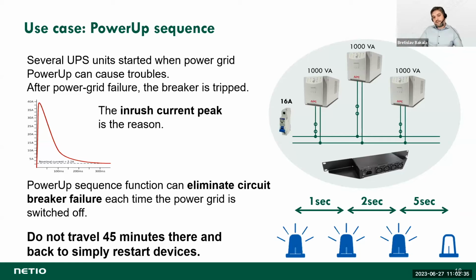This inrush current is the reason why. It's not an issue just for UPS, but for all standard switching power supplies used in every IT equipment today, even laptops and monitors. It depends whether you have bigger servers, AV equipment, or IT equipment in general - all of these devices use power sources with this high inrush current peak. With the power up sequence, you can balance it over time, so the circuit breaker will not be activated.